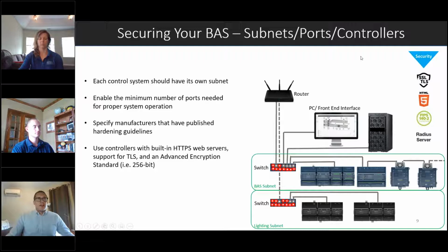So, moving on to what's actually in your building. So this is really looking at everything in your building. You do want to segment different networks. So your lighting should be separate from your controls, should be separate from your security system. They should all have their own subnets that they live on. That helps with security, ensures the communication stays where it should be within those networks.